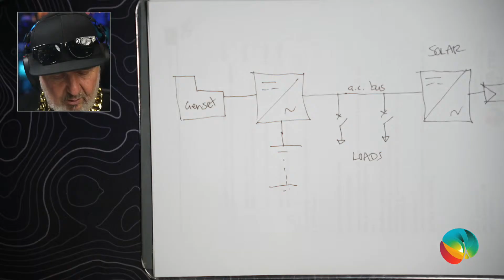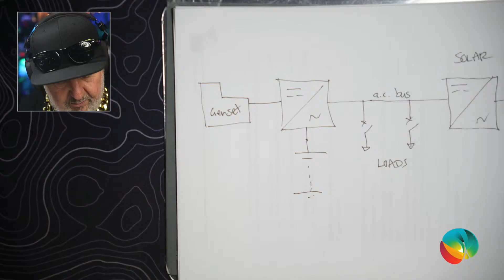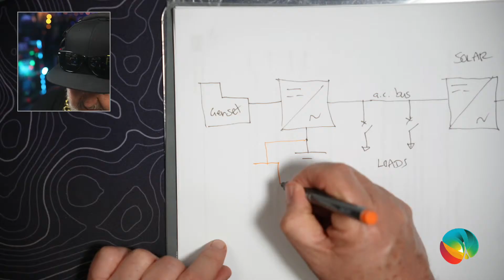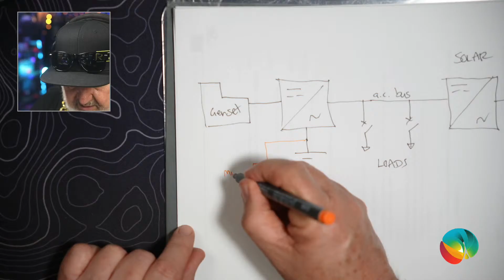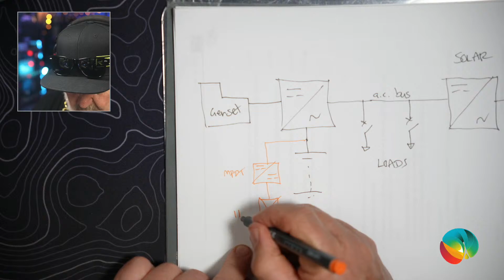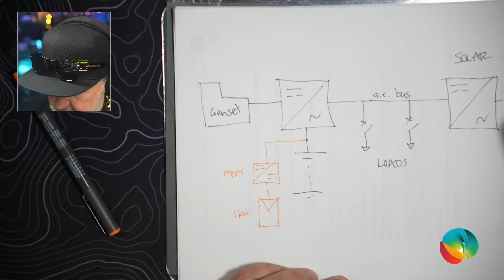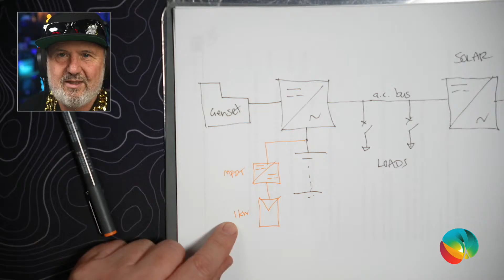So what a black start system using PV does is DC couple - I'll do it in a different color - a dedicated solar charger. So DC to DC solar charging directly to the battery system. Let's say that's an MPPT, and this might actually be quite a small array, maybe just 1 kilowatt of panels, whereas our main system is 20 kilowatts. You might think, what's the purpose of having just a little 1 kilowatt system connected to the battery?